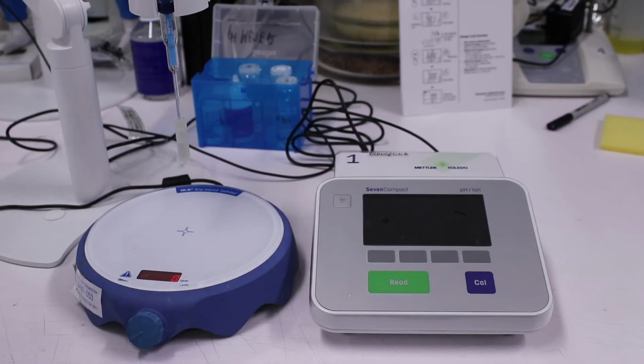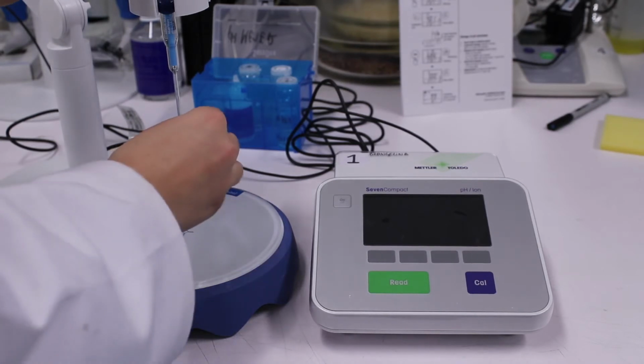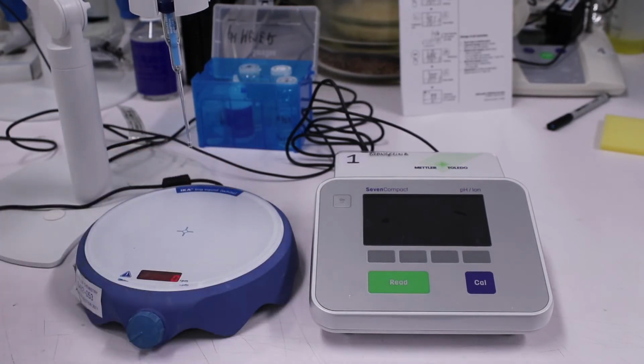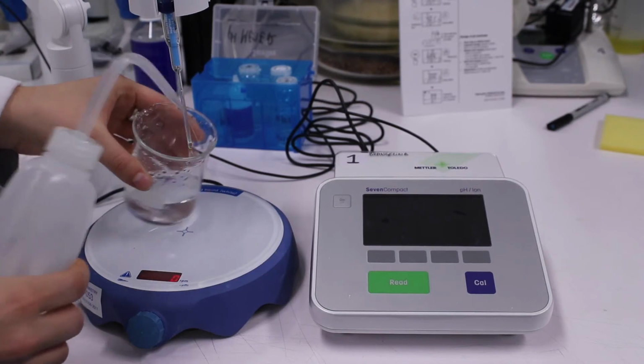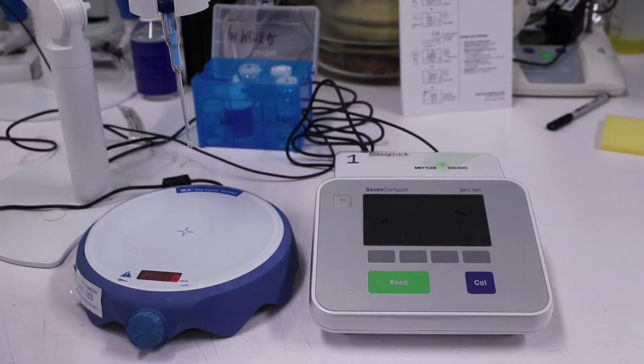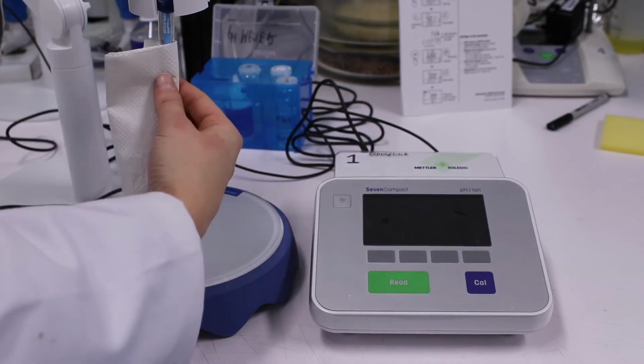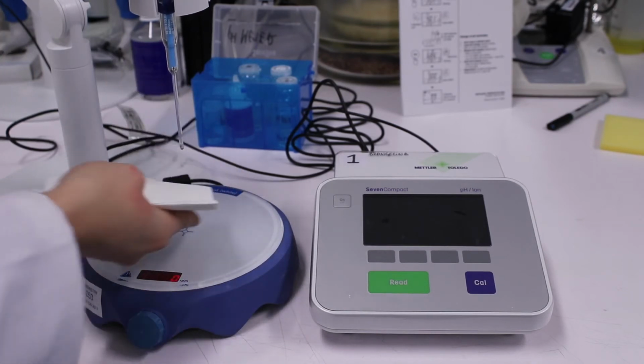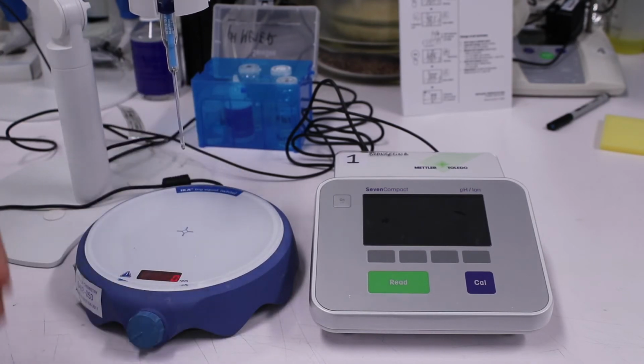Now I'm going to show you basic maintenance of the electrode probe. Once you finish the reading, you will probably have some water droplets in the electrode. Please make sure that you do not wipe the membrane like that. Simply dabbing it on the end should be sufficient. If you wipe the membrane, you can cause damage which might cause inaccurate readings.